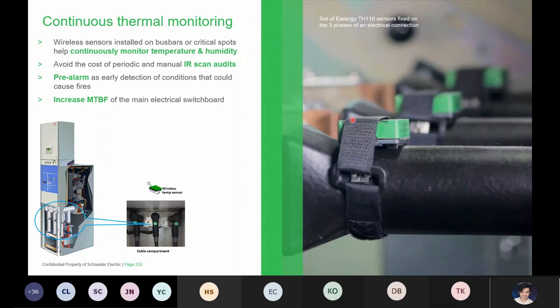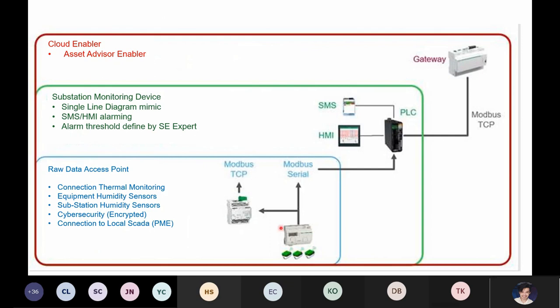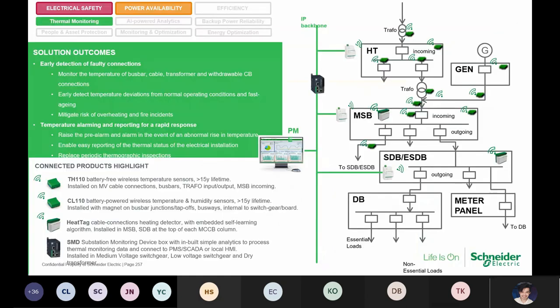This picture just shows that it's in contact with the bus bar. So this is how it actually works. From the sensors, it goes into a gateway, and from the gateway, it can go into a controller. The controller can be monitored, sending information to your phone via SMS, or via HMI. You can also see certain alarm trending on HMI. For analytics to take place, we use cloud. You have a gateway here, put in a 4G SIM card, and the information can be transmitted into cloud. So these are the key components.